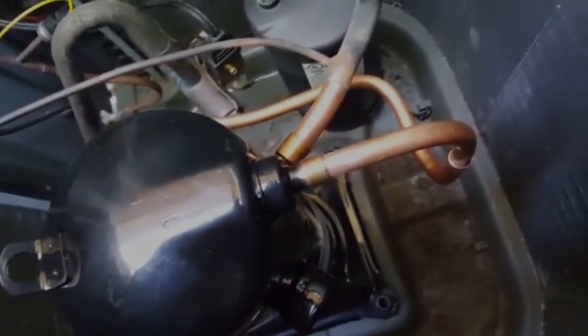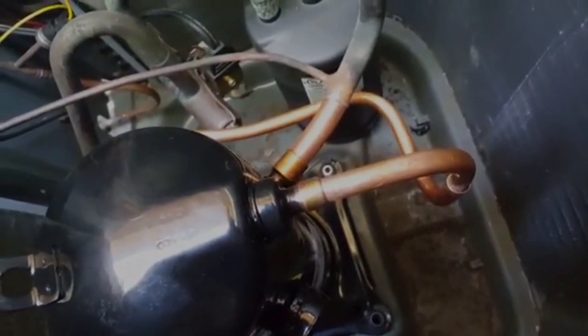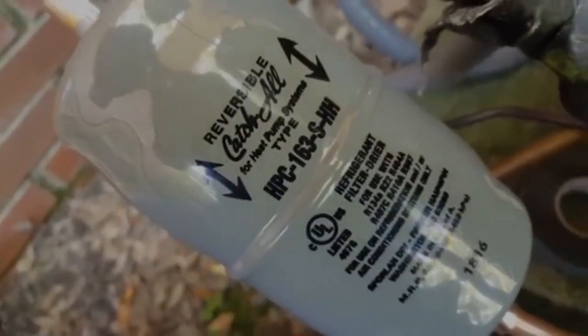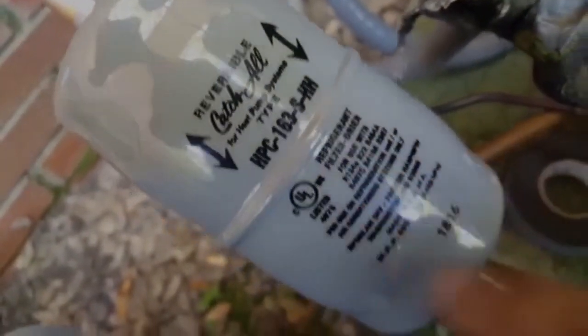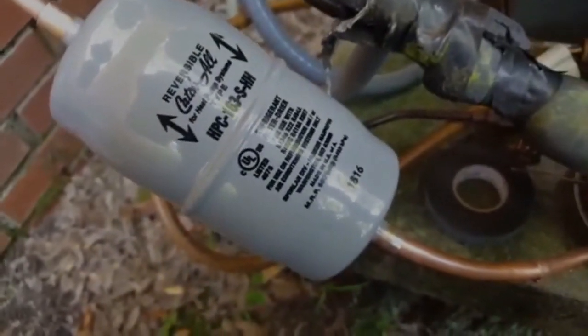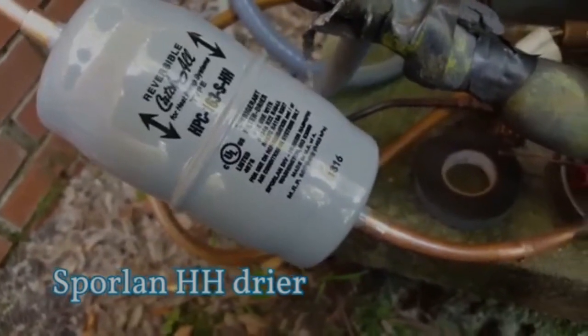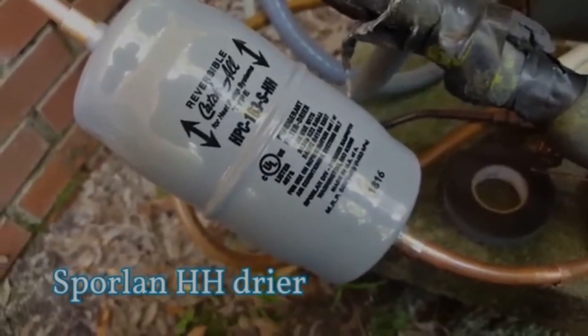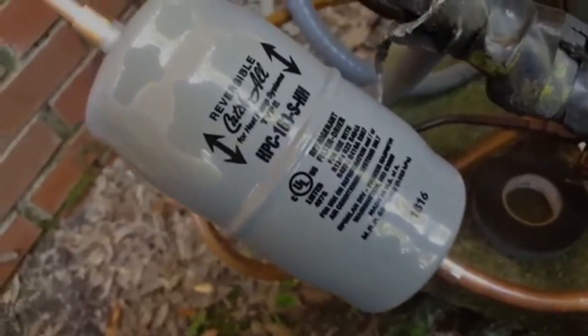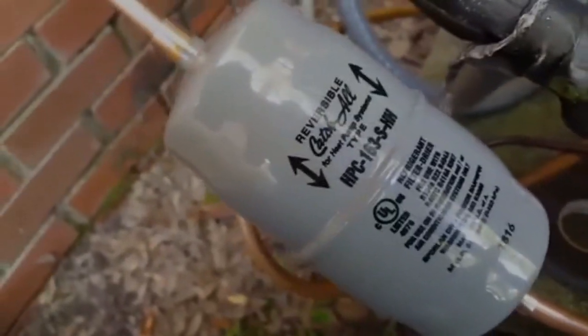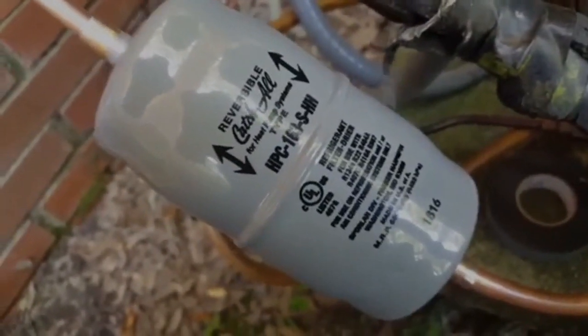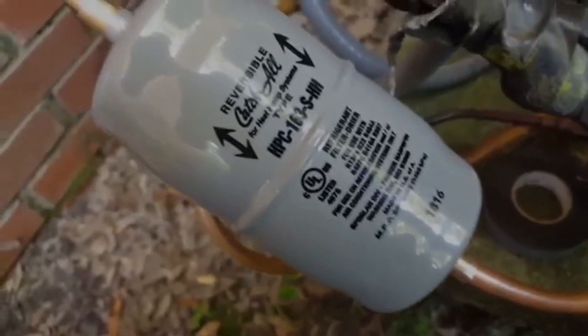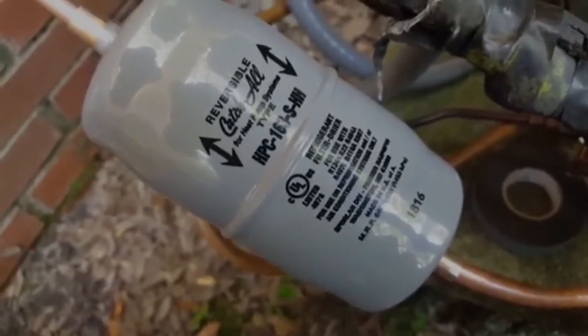So I'm going to braze this up, flow a little nitrogen, then switch to the dryer on the outside. I've got a reversible Sporlan catch-all dryer, built for cleaning up systems that have had issues. I'll leave it in there, let the system run for a few weeks, come back and check it, and likely swap it out again. But give it at least a week. Knowing me, I'll probably be held away a few weeks before I get back to check it.